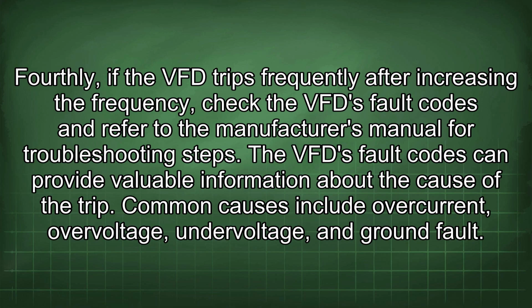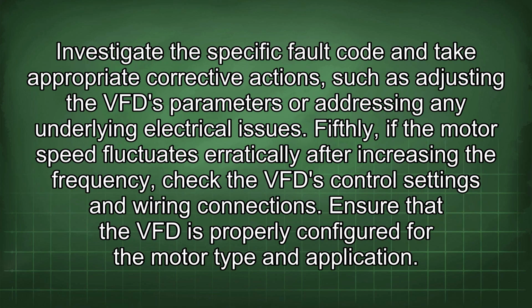Fourthly, if the VFD trips frequently after increasing the frequency, check the VFD fault codes and refer to the manufacturer's manual for troubleshooting steps. The VFD fault codes can provide valuable information about the cause of the trip. Common causes include overcurrent, overvoltage, undervoltage, and ground fault. Investigate the specific fault code and take appropriate corrective actions, such as adjusting the VFD parameters or addressing any underlying electrical issues.